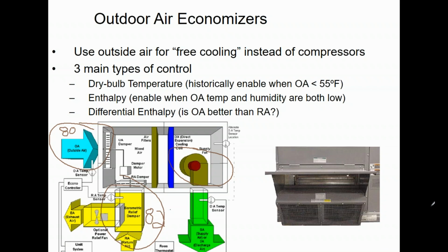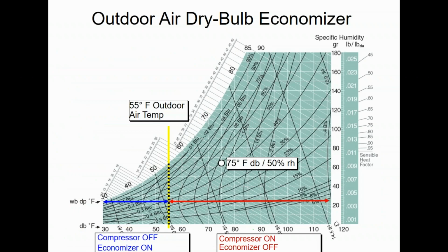My penmanship is fantastic. I'm well aware of that. All right, so that's kind of the deal with that. So from a code perspective, let me get back to my regular arrow. What's happening on my psychrometric chart is that if it's below 55 degrees, I'm going to get my free cooling. Right down here, I shouldn't have picked green. That was a bad color choice. John Madden would be so disappointed in my skill set right now. We'll do red, right? Below 55 degrees, give me free cooling. If it's above 55 degrees, give me compression. That's the historical way that we would have handled that, right?